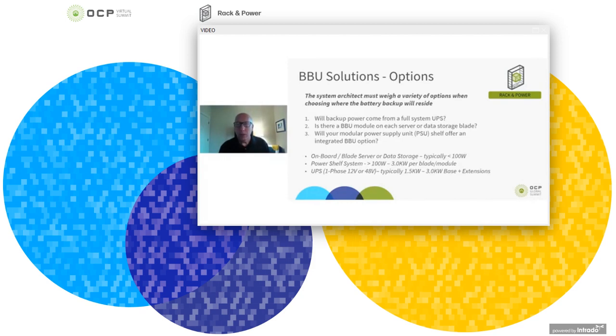There are a couple of different power ranges you'll traditionally see in each type of application. Onboard the blade server, supporting just that blade, maybe 1U or 2U high, that may be 100 to 200 watts. A power shelf system, though, could be anywhere from 100-200 watts up to 3 kilowatts per blade or module.